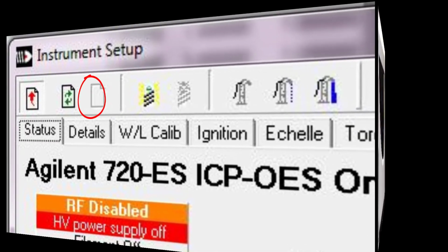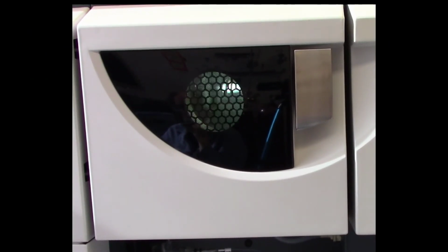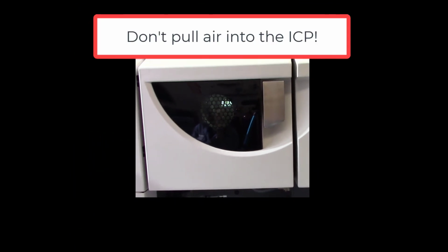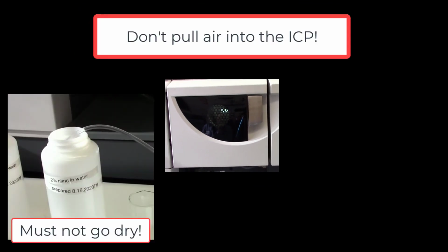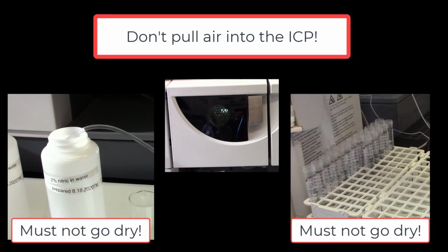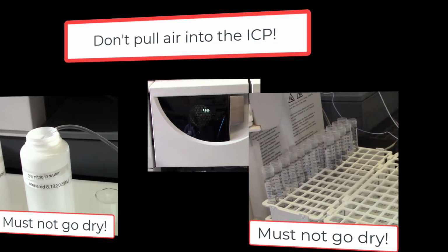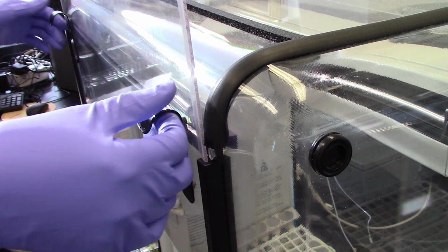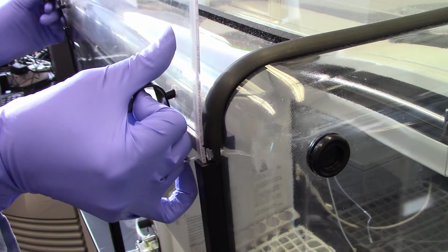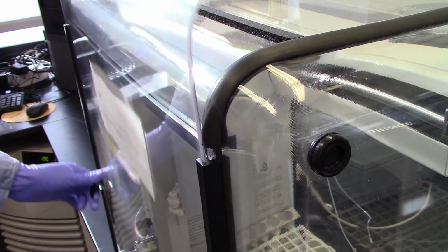It will take about a minute and a half for the system to ignite, and you'll see the torch as a blue light through the window on the front of the instrument. From this point on, you must be sure that you don't pull an excess of air into your torch. This means you need to keep an eye on your wash solution and your samples to be sure that nothing goes dry during your sample run. Before proceeding, lower the door of the auto sampler.